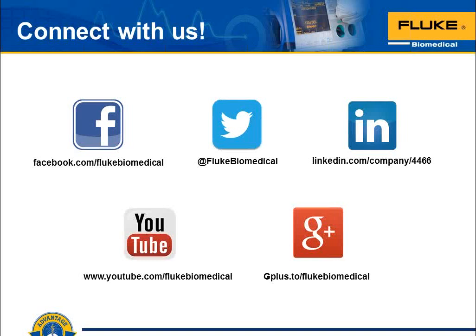I get as close as I can, make the measurement, and if I have any concern, I get a hold of the manufacturer of that particular ESU model and do a little consulting with them. If they've picked a really non-standard load value, that means they're trying to control you and your spending, requiring you to buy extra test devices just to test electrosurgery unit generators as a category. There isn't any reason why they should do that. The requirements laid down by the standards are sufficient to make sure these medical devices are safe and effective for clinical use. Anything else is a power play, so don't get taken.